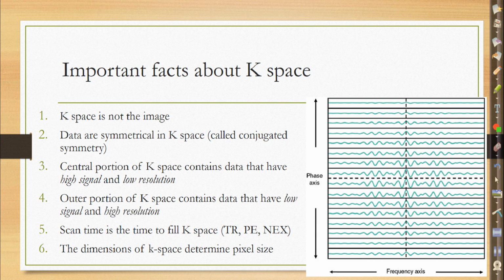So sometimes in MRI, you can put that little live box up, and it shows you one slice as they are acquired. So it takes like 20 to 30 seconds for an actual slice to show up, and that 20 to 30 seconds is the time where we're filling K-space. Correct. But usually you have to wait a little bit longer for it to go through that mathematical process, which doesn't take very long, it could be milliseconds for that to occur. But then an image shows up. But that's just one slice of the pulse sequence. And then you acquire another slice, and then another slice. And so once you have all the slices acquired, you'll have your complete pulse sequence. But good, yeah. Okay, so rule number one, K-space is not the image. It's just basically where we're storing all that signal.